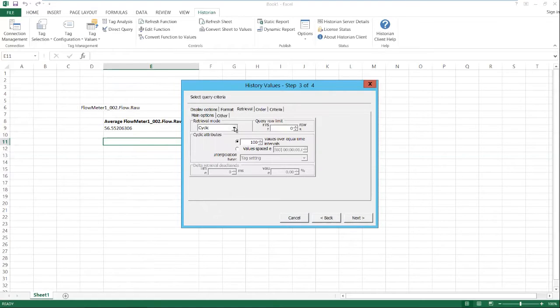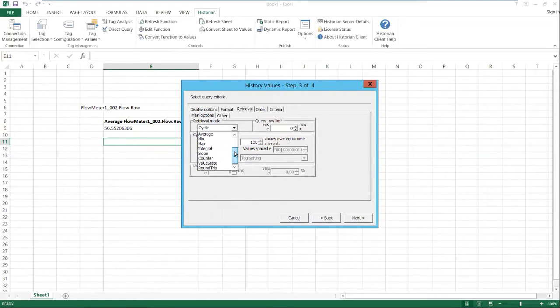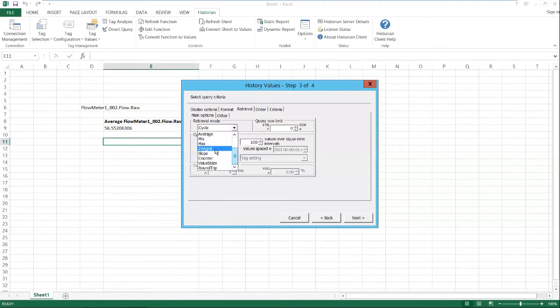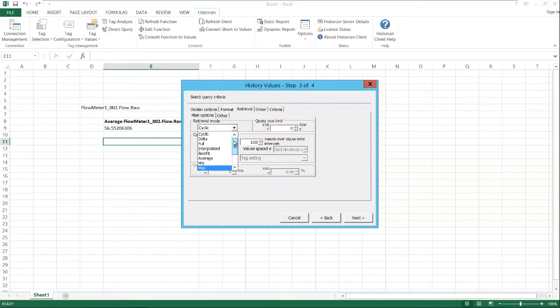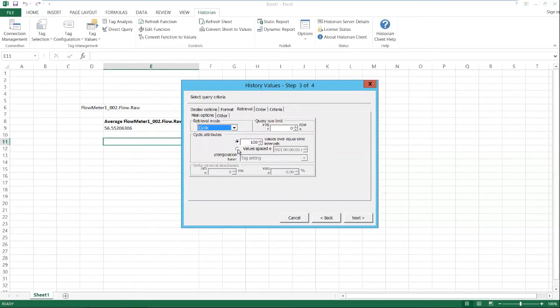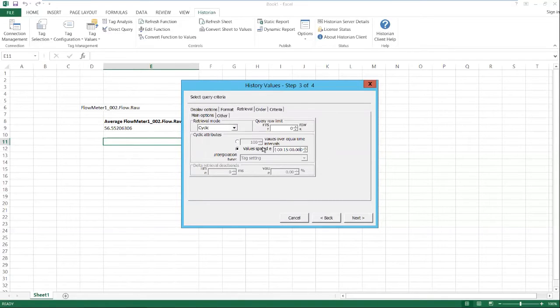And notice the available retrieval modes in historian client here. We could do uptime, downtime. We can do totalized flow, min max averages. Or to start off with here, we are just going to do a cyclic retrieval, which will let us retrieve interval-based data. And since most regulatory reports want 15 minute interval data, we'll do values spaced every 15 minutes.